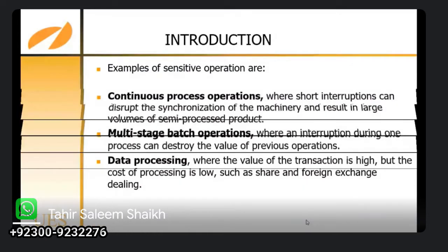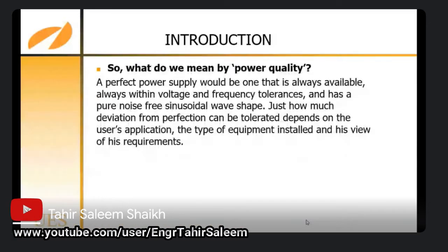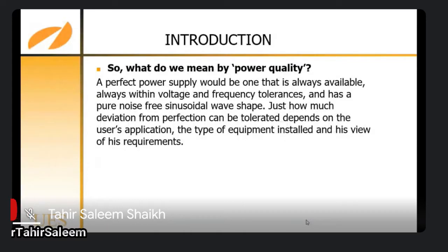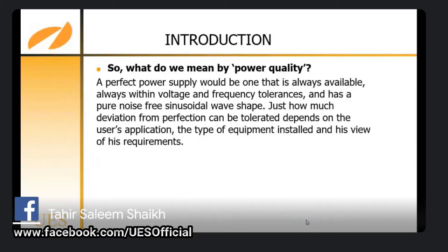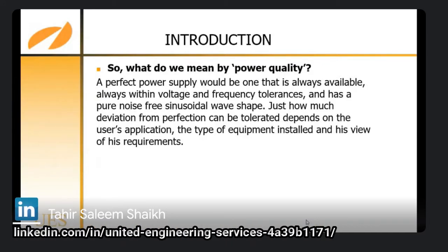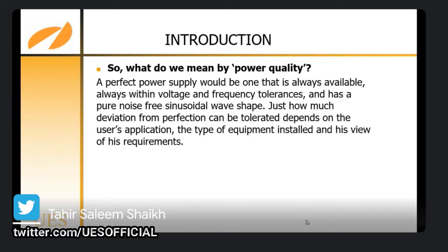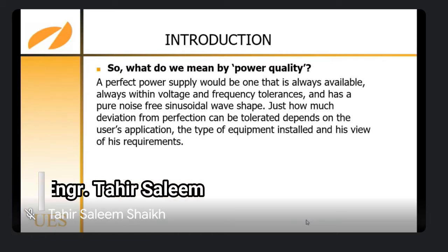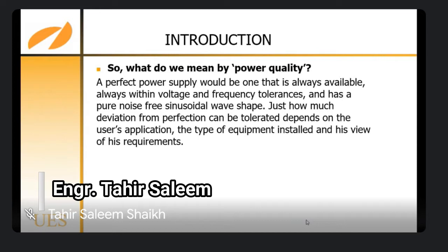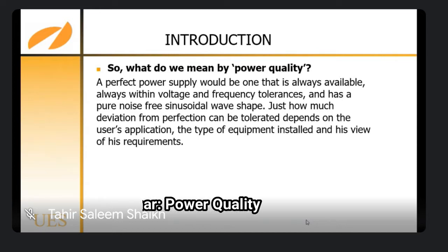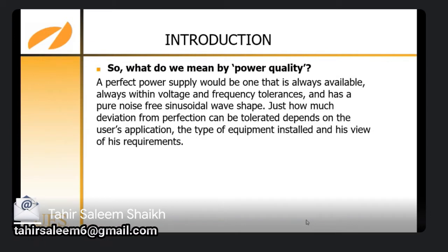So what to do? A perfect power supply would be one that is always available, always within voltage and frequency tolerance, and has a pure, noise-free sinusoidal wave shape. Just how much deviation from perfection can be tolerated depends on the user's application, the type of equipment installed, and his view of this requirement. So, like mineral water, you need pure power quality within limits of voltage tolerance, frequency tolerance, noise reduction, etc. This will run your plant smoothly, maintenance free.